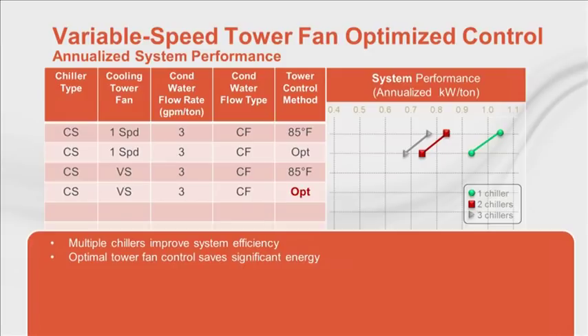The next alternative begins with the base case, but applies a variable speed fan to the cooling tower. Just putting a VFD on the cooling tower fan reduced energy consumption more than applying optimal control to a fixed speed tower fan. We can see why 90.1 required tower fan speed control back in 1999.